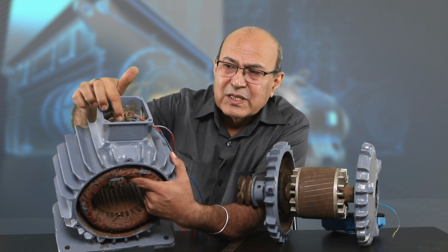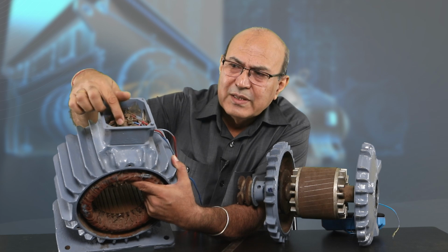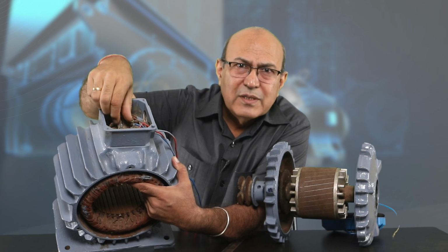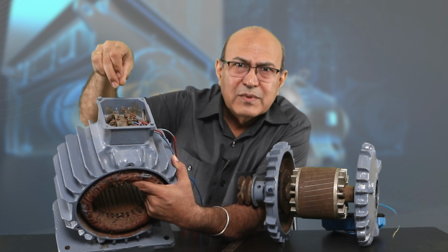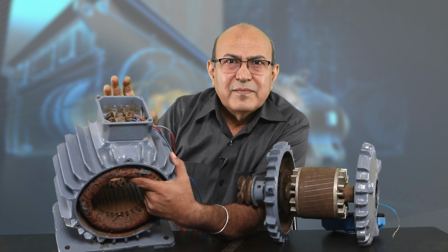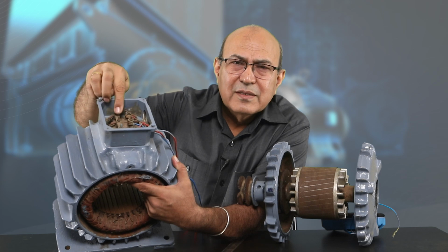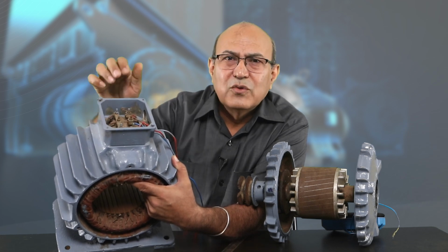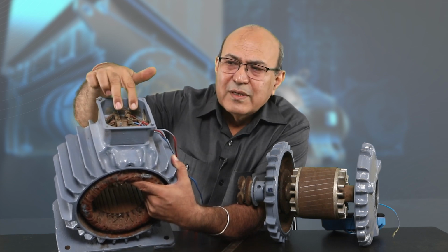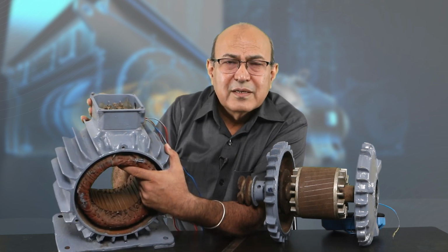Of course, you will find 3 strips here, copper connecting strips. These 3 terminals are short circuited. If you just open these terminals and remove these strips, it is neither star nor delta. If you want to make it a star, then place like this, these 3 terminals are short circuited, it is now a star connected stator. If this point is connected to this, and the last one is this to this, then it is connected in delta.